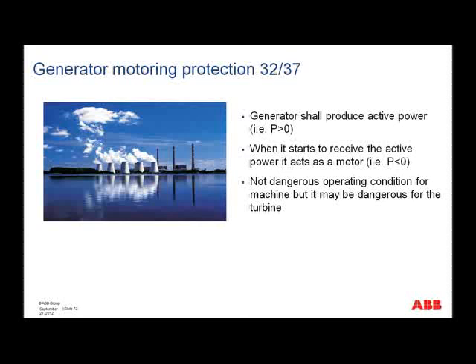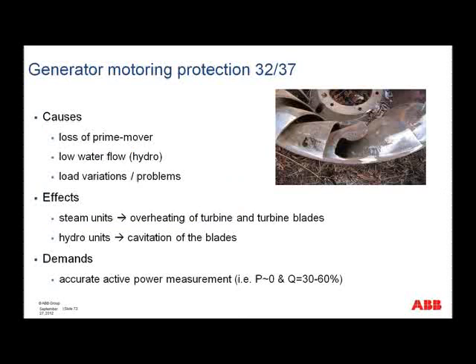Generator motoring. Now, as we all know, a generator should produce active power. If it starts to receive active power, it then would act as a motor. And although this is not a problem for the generator itself, it could be rather dangerous for the turbine. So here we have the causes, we have the effects, but the important thing to look at is the demands on the measurement, because we need to measure the active power very, very close to the zero mark, but actually the Q could be quite high.